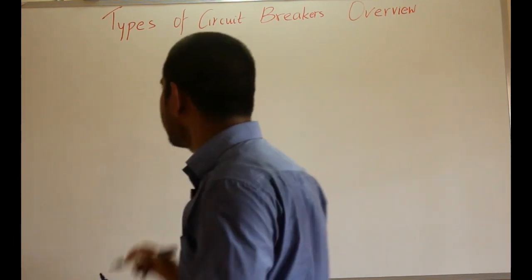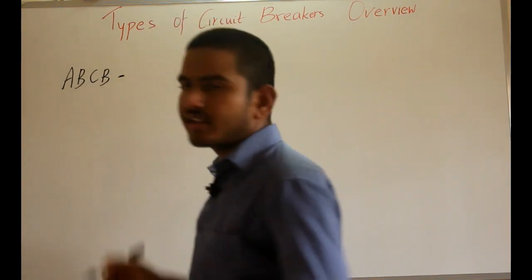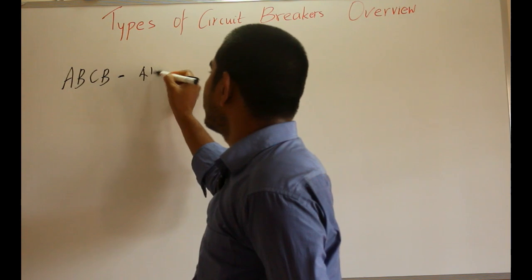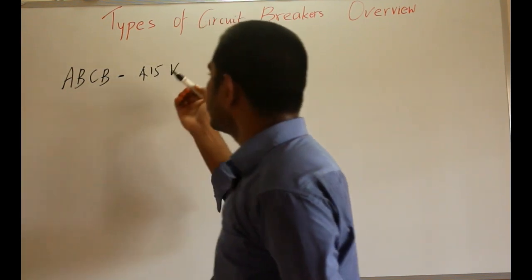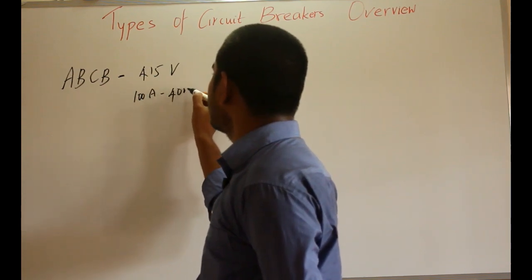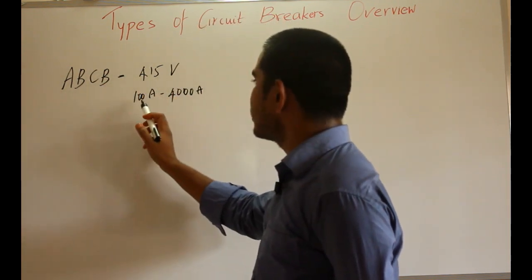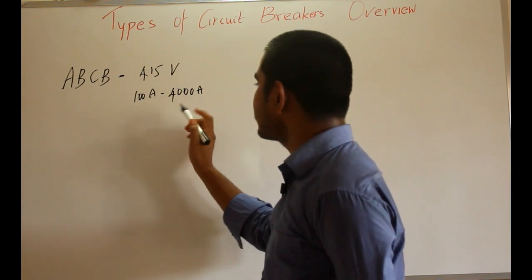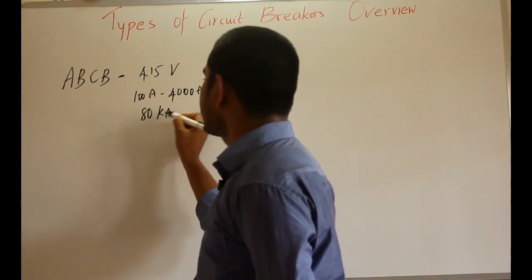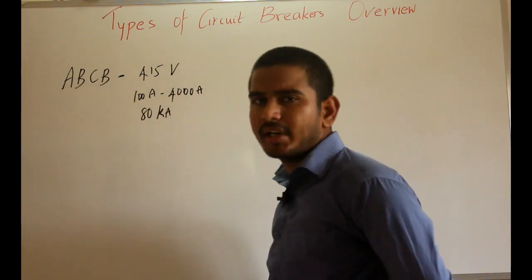The first breaker is the air break circuit breaker. Air break circuit breakers are employed for voltages up to 415 volts and current ranging from 100 amperes to 4000 amperes. The breaking capacity recorded is 80 kilo amperes. The air here is at normal temperature and pressure — air blast is different from normal air.